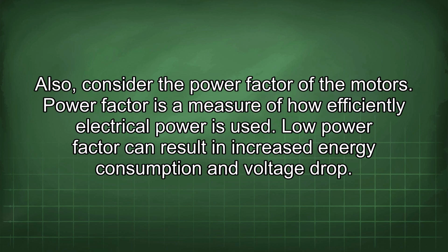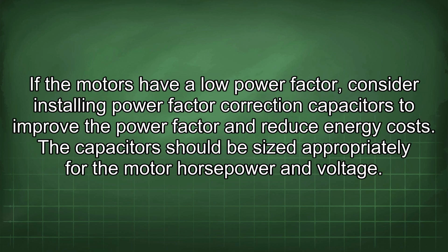Also, consider the power factor of the motors. Power factor is a measure of how efficiently electrical power is used. Low power factor can result in increased energy consumption and voltage drop. If the motors have a low power factor, consider installing power factor correction capacitors to improve the power factor and reduce energy costs. The capacitor should be sized appropriately for the motor horsepower and voltage.